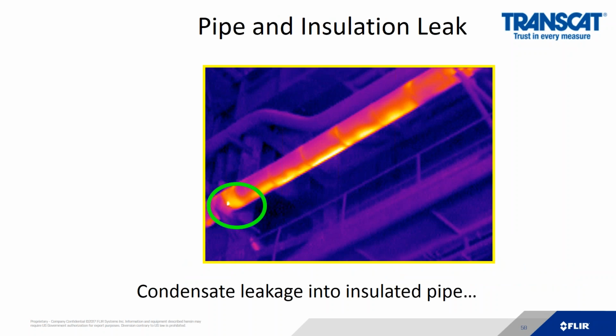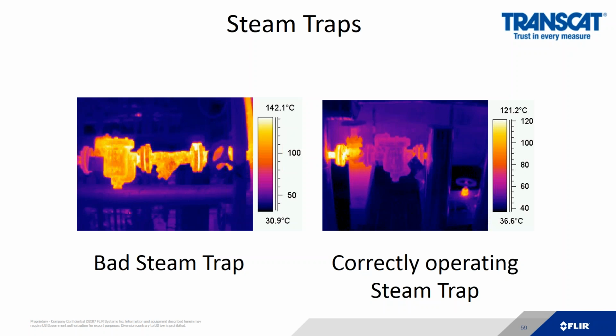If you're in a manufacturing plant and you want to see if there is leaking in your piping system, here is an example of a condensate leaking into an insulated pipe. We can see the hot spot. The green circle is identifying that, and you can see the water and saturated insulation underneath the metal cladding right there. Companies like to use our cameras in steam traps. Again, an infrared camera is a second tool to ultrasound for finding steam trap problems, but it can be used to help identify certain problems within steam traps.